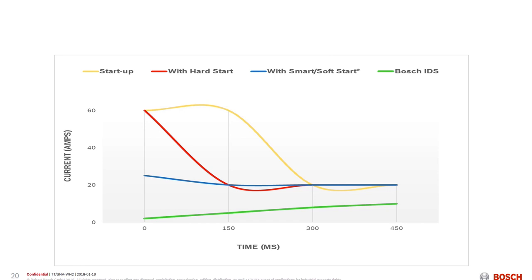I'm going to try to combat that with a hard start kit, something that's going to take that and reduce those amps. If I had a Copeland compressor, I might even be able to put a soft start kit on that particular device. Anyway, I'm always going to be starting somewhere around 21 to 18 amps, again having the possibility of dimming the lights. My particular system, whether it's a 5-ton or a 3-ton, always starts at the lowest denominator of the amp draw. My unit will always start at less than 2 amps, and then go toward the comfort level that you need.